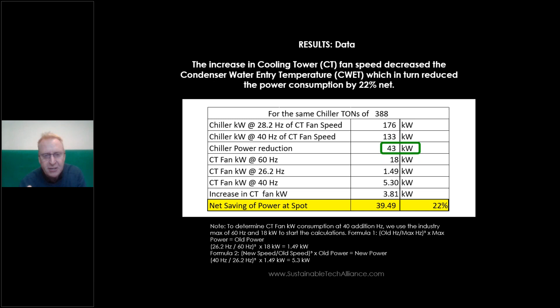Now, the facility team asked us on the job site, well, how could we possibly go in every hour to determine the exact right hertz increase on the cooling tower to balance the condenser water entry temperature? And we said, how about you don't do anything? How about the algorithm does the work for you? This is adding a brain to an existing facility that already has equipment. The result, by the way, ends up being 15 to 40% of the consumption of energy in actual savings.